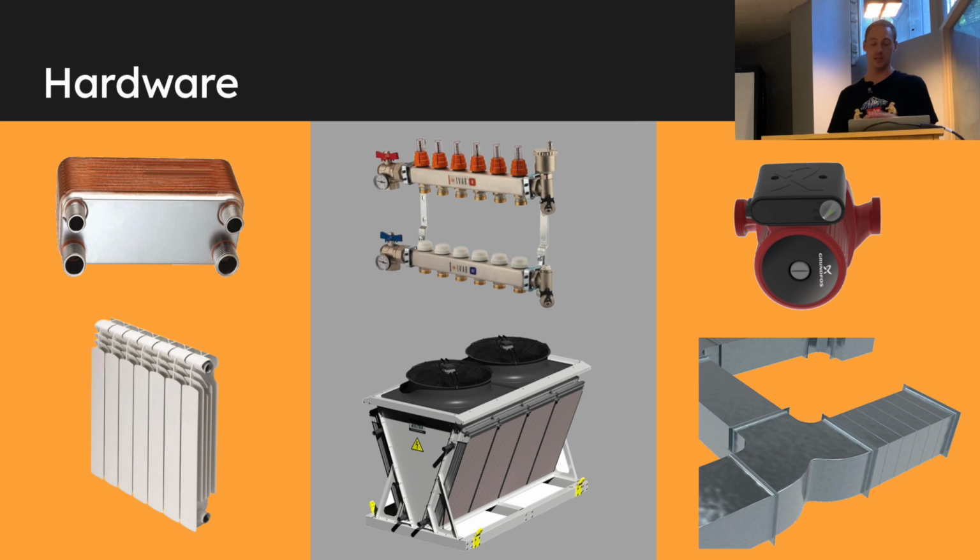So this would be more for not reusing the heat, but rejecting the heat. What this does, it's like the radiator, but it's just a bunch of tubes with many, many more fins and then fans on top that ramp up and down to force air through it. It's called forced convection. And that's how most Bitcoin miners right now, the large scale, reject that heat.